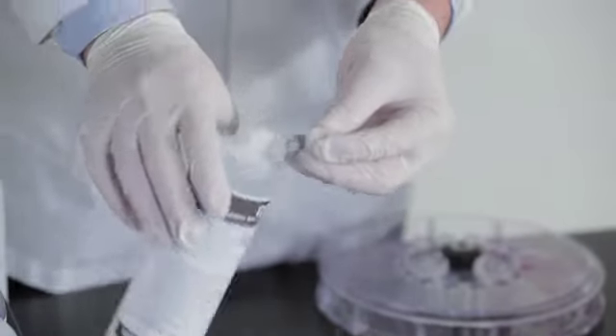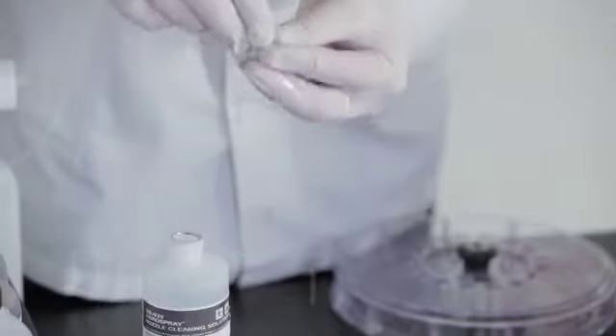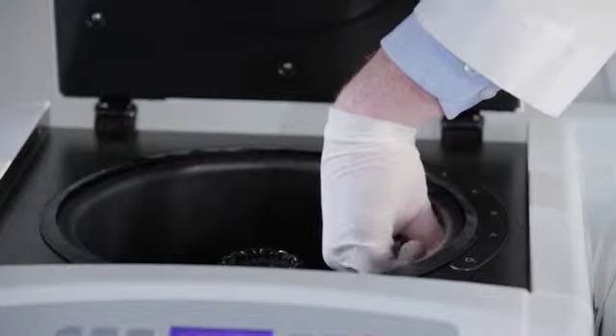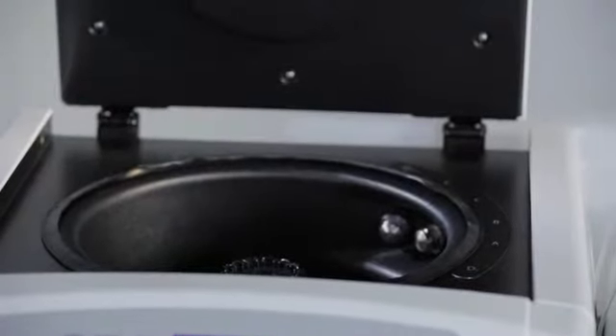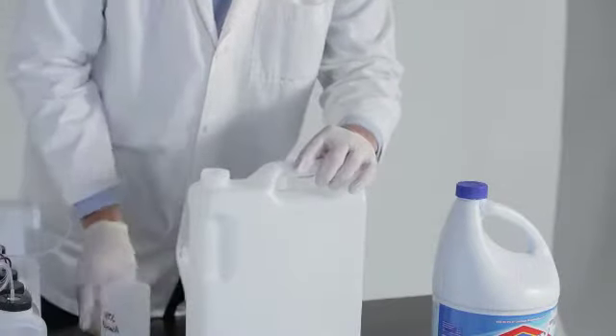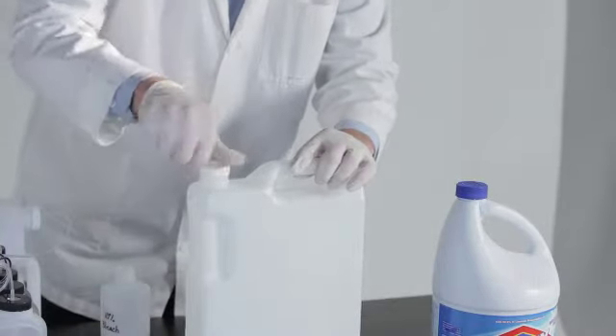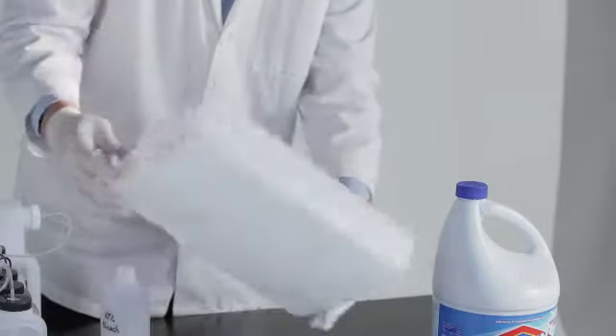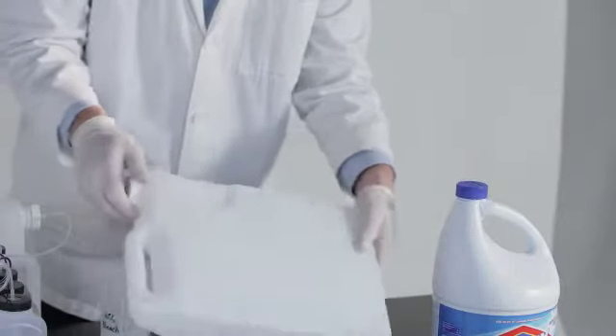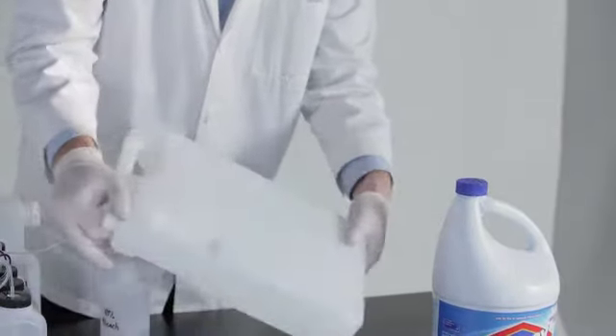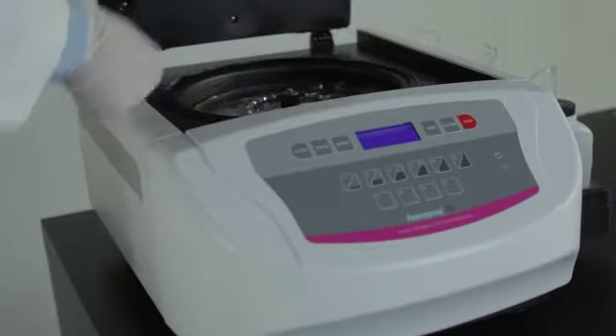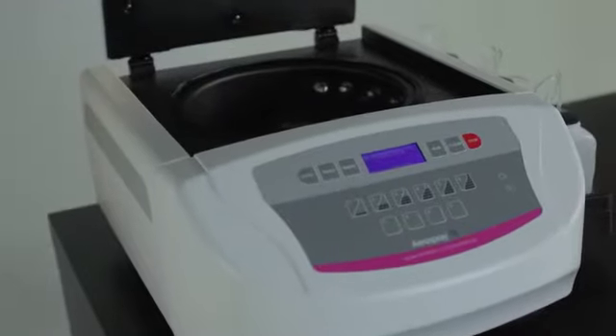Product SS230 is a cleaning product that cleans the nozzles very well. This product should be used when cleaning the nozzles. Be sure not to lose the mixing insert when cleaning the nozzle. The 5-liter bottle used on the A line should be cleaned with a 10% bleach solution each month when it is emptied. Refer to the applications manual for more information regarding preventive maintenance. The Aerospray TB stainer is designed to spray carbofuchsin or fluorescent stains. These stains are used to stain acid-fast bacilli, mainly Mycobacterium tuberculosis.